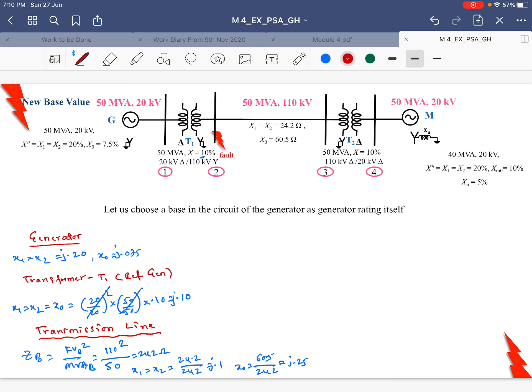Therefore, x1 equals x2 equals x naught equals kV old. kV old is 110, kV new is 110, MVA new 50, MVA old is 50. Therefore it remains the same. That is, 110 divided by 110 whole square into 50 by 50 into 0.1, equal to 0.1 per unit value you are getting. That is for transformer 2.